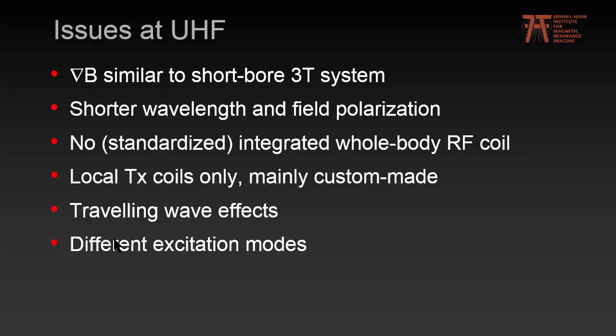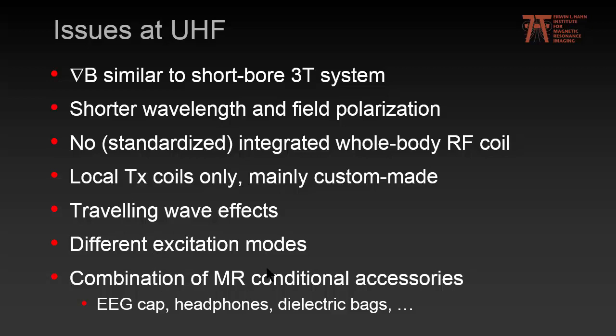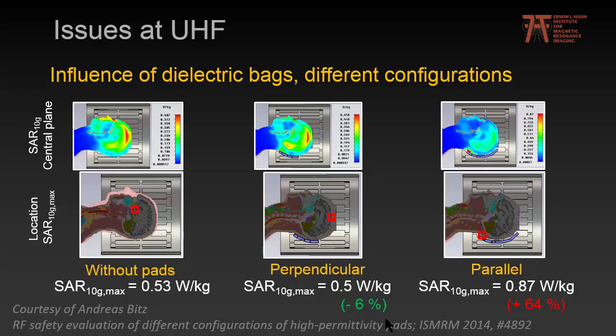Other ultra-high field considerations include traveling wave effects and the production of different excitation modes, both of which complicate standardized test methods. An open question is how to combine different MR-conditional accessories — such as EEG caps, headphones, or dielectric pads — in a patient who already has an implant, since dielectric pad configuration can influence SAR.